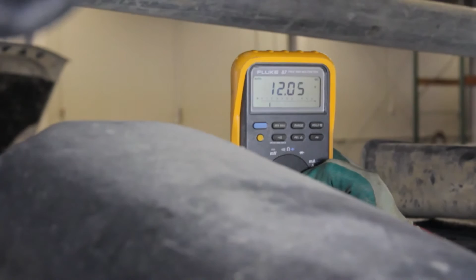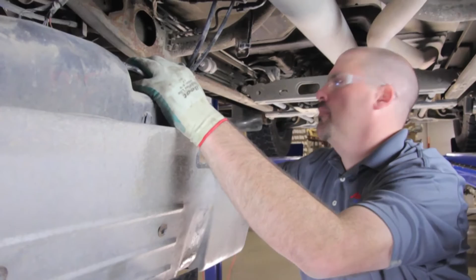We got a 0.89 -- again we really want to see this voltage drop at less than 0.5 volt. Obviously there's an issue in the positive circuit. We've got some high resistance going on, and we may have a relay or a connection that's actually causing that. That would require us to segment the circuit on the positive side, go back to the next connector, and again do your voltage drop until we find the problem.